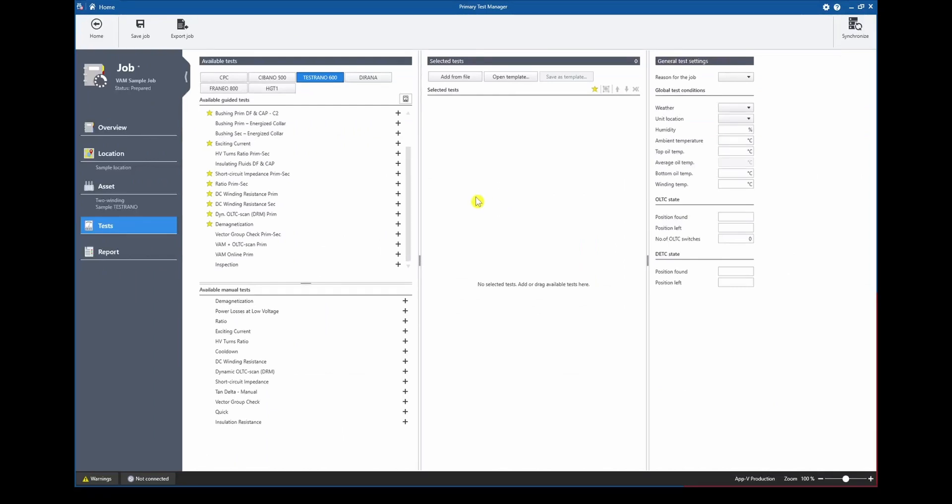With PTM 4.90 we have added a three-phase output option to the existing dynamic OLTC scan measurement for the Testrano 600. On the one hand this allows to reduce the testing time as all three phases are tested simultaneously and in addition the user can now analyze any deviations in timings regarding all three phases.